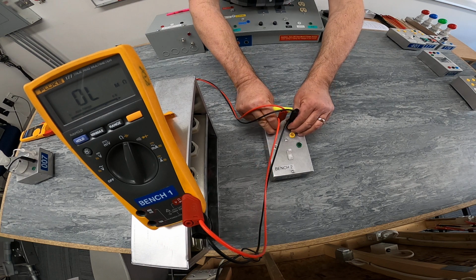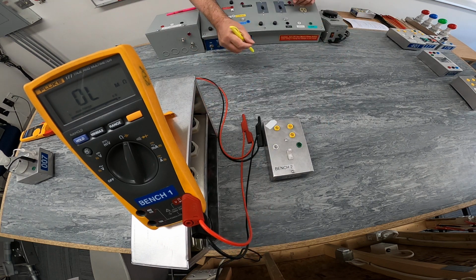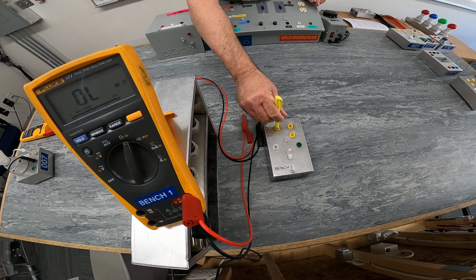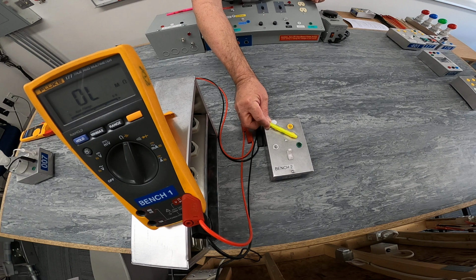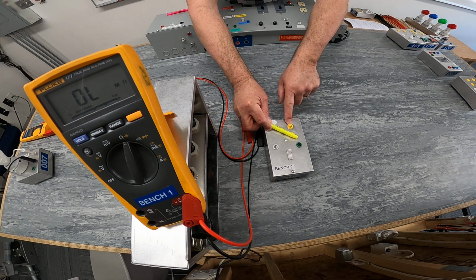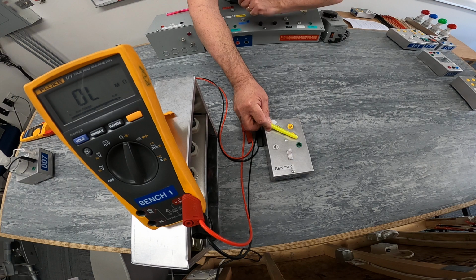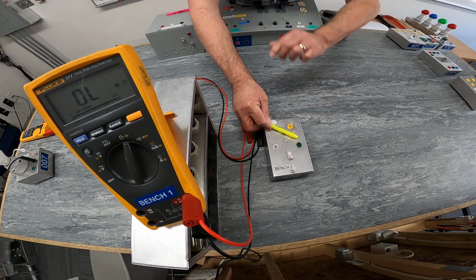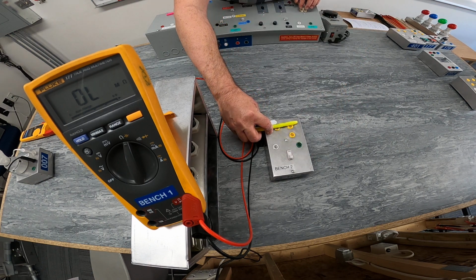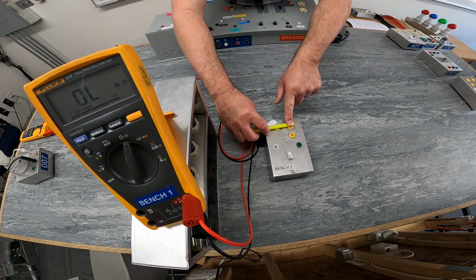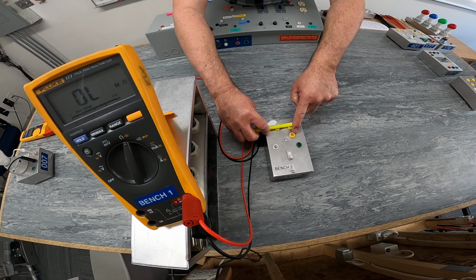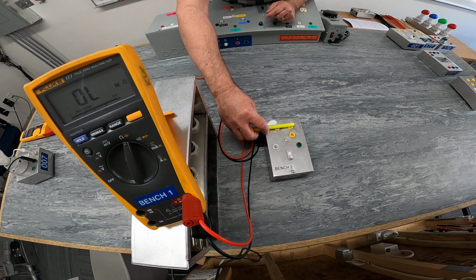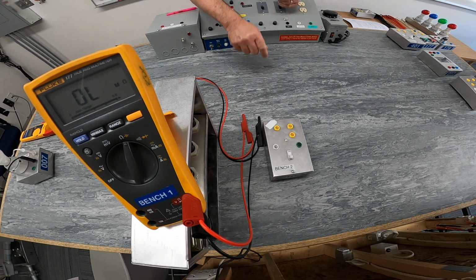Typically, I'm just going to pull my leads out for a second here, just to indicate that this here is your common connection, and it will either switch between these 2 points and make a connection while these 2 are open and these 2 are open. Then when we flip the switch, it will make a connection from the common down to here. Now we have a closed switch here. Between these 2 terminals are open, and between these 2 terminals they are always open. So that's the functionality of a 3-way switch.